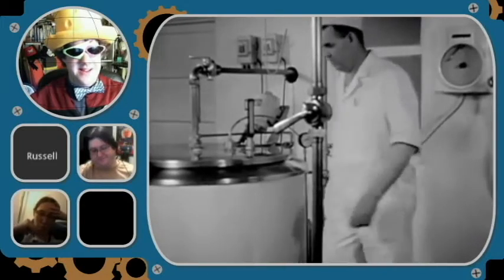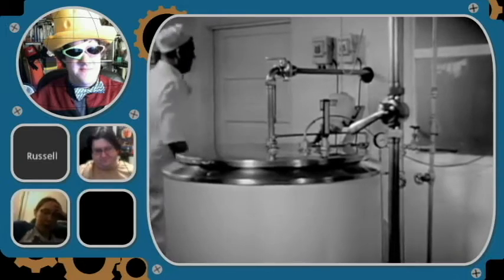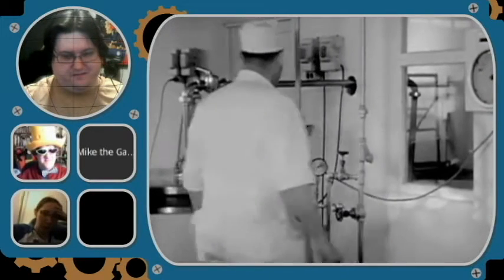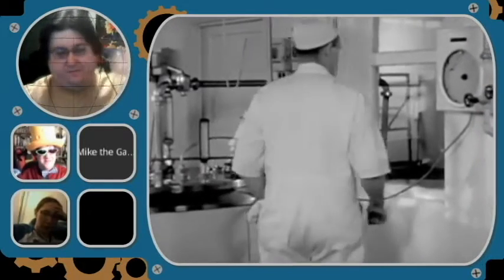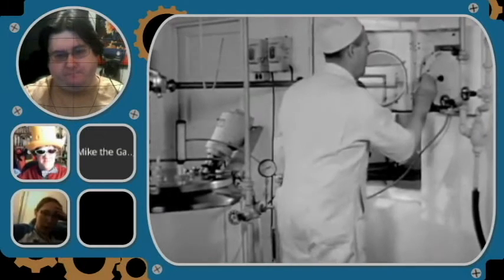It's complicated. When the milk reaches pasteurization temperature, turn off the water jacket circulating pump, but leave the agitator on during the entire pasteurization holding time. Remember that the indicating thermometer gives you the accurate milk temperature. But to be sure the recording thermometer is also accurate, compare it with the indicating thermometer once during pasteurization, usually after the milk has been at pasteurizing temperature for about 10 minutes.